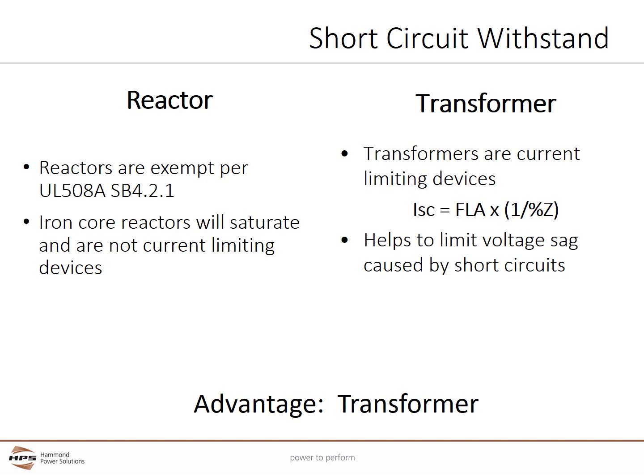Short circuit withstand. During a short circuit fault, a transformer acts as a current limiting device. A transformer limits the maximum short circuit current to the inverse of the impedance times the full load amps. Example, if a transformer has 5% impedance and is rated for 100 amps, the inverse of 5% is 1 divided by 0.05, which equals 20. This transformer's maximum short circuit current would be 20 times 100 amps, or 2,000 amps. An iron core reactor, on the other hand, will have the core saturate during high currents found in short circuits. Upon saturation, the reactor basically operates as a wire and doesn't provide any current limiting. Therefore, transformers have an advantage when faced with a short circuit fault.